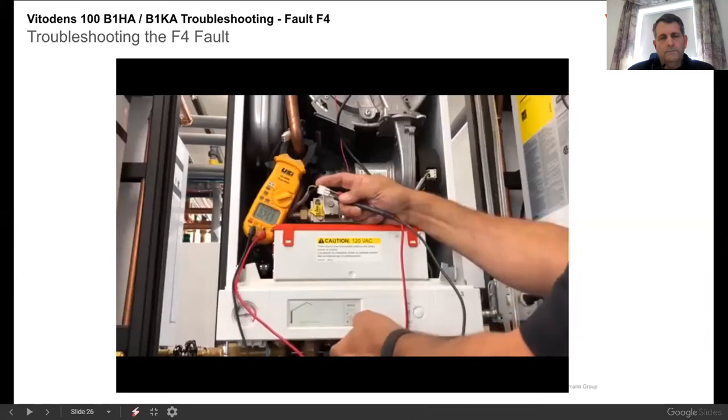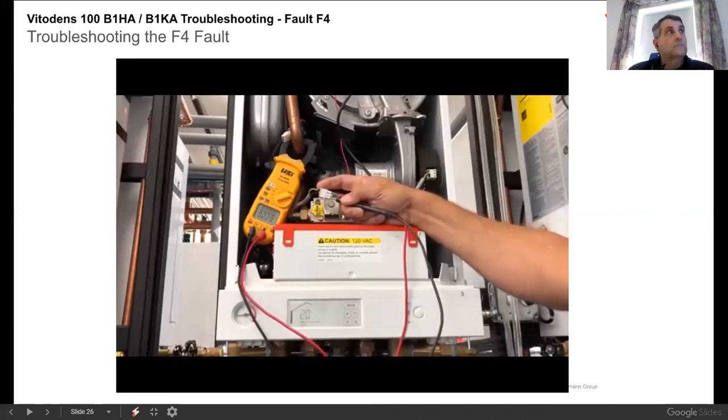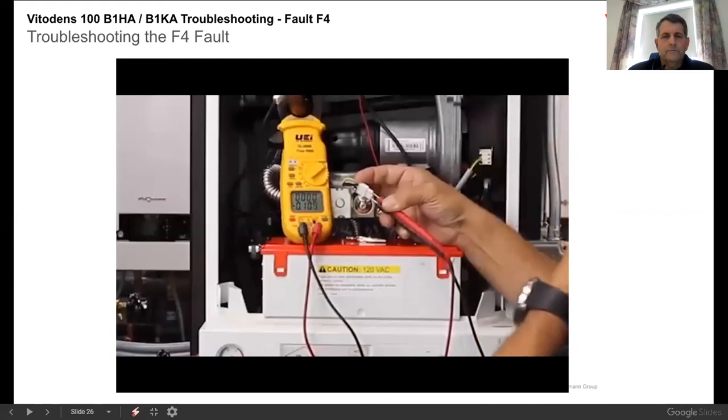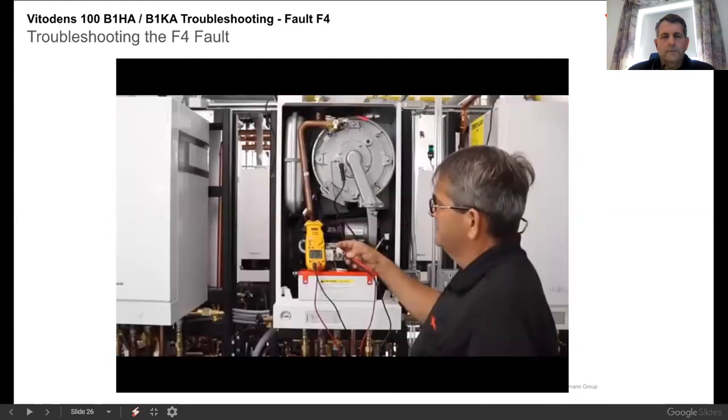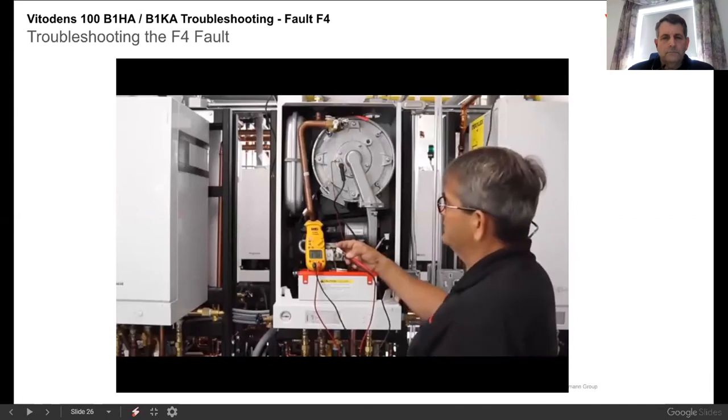We'll go to service here to get the boiler to fire. I'll start it with 20%. Hit okay. We'll see the boiler fire. So there you go, there's your 107 VDC, 106, 108. So now you can see that we have the VDC reading on the boiler.